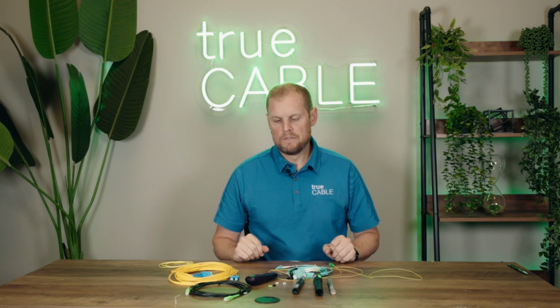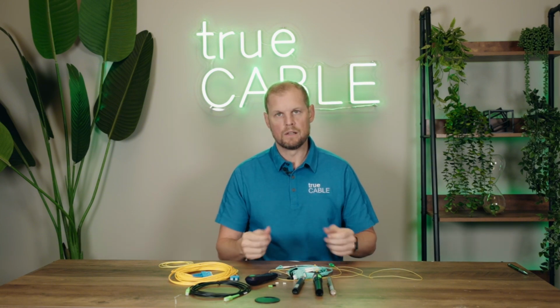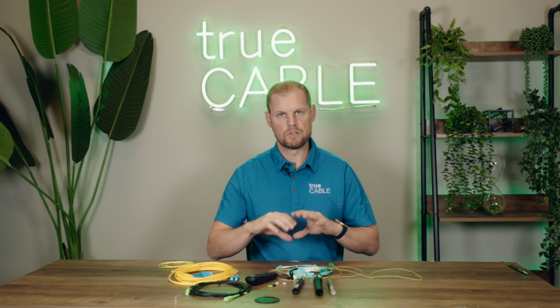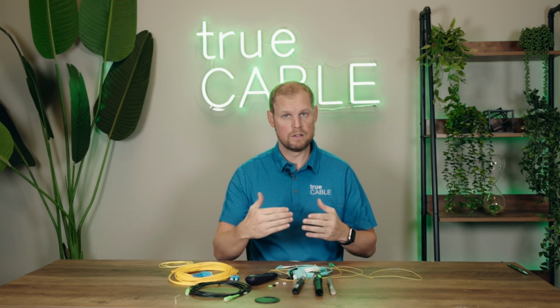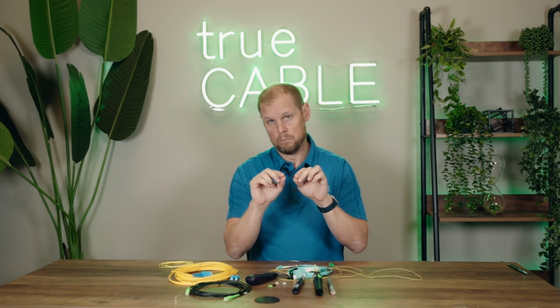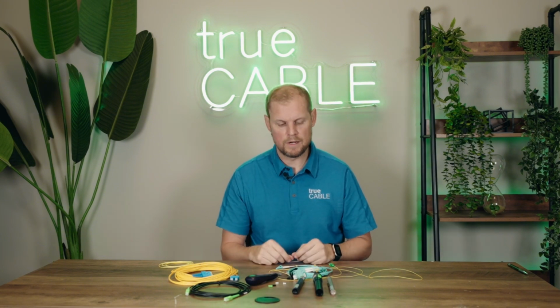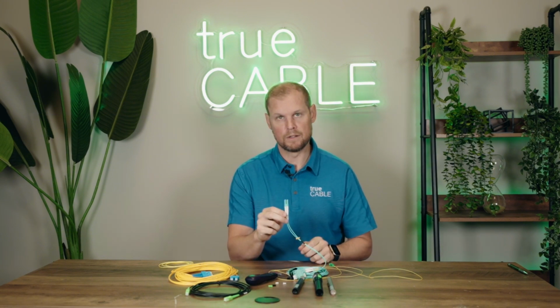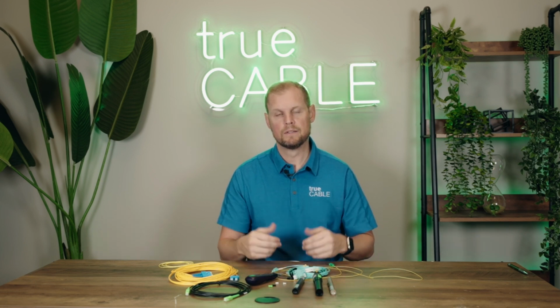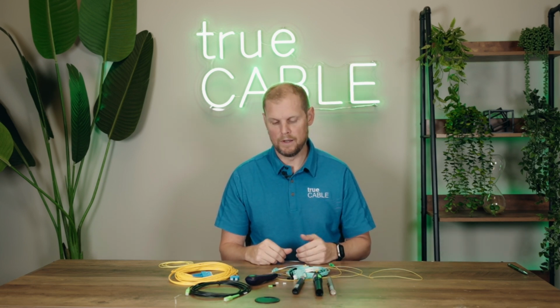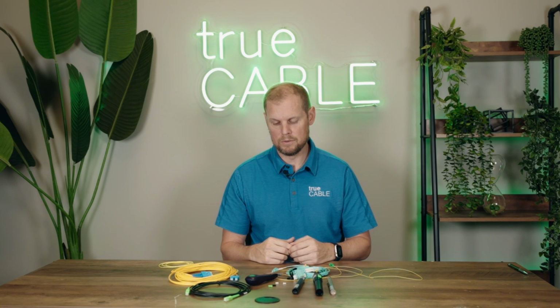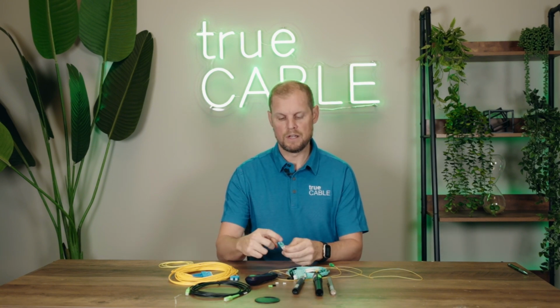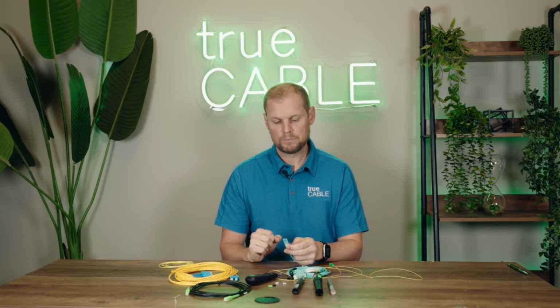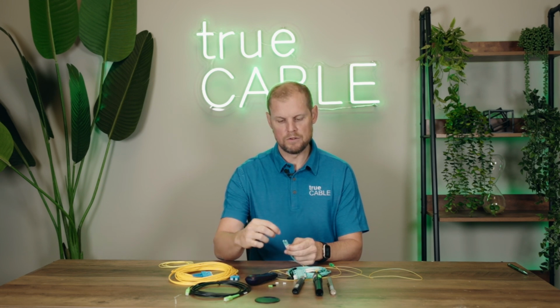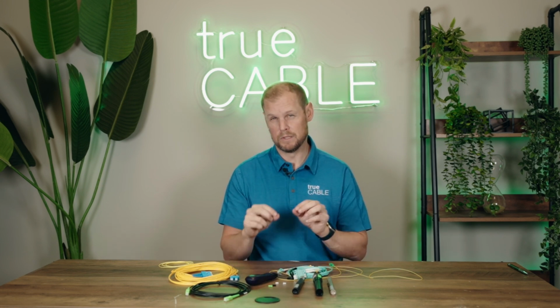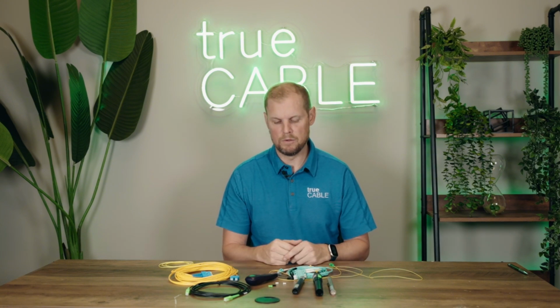When testing with your VFL, make sure you're plugging it directly into the end face of the connector, checking the connector end face and boot for any light loss, as well as at the far end to make sure there's adequate light being exposed. One quick way to verify this is to shine it down one end of a duplex connection, and it might be really bright, then shine it down the other end and it's really dim. That's another indicator you may have an issue.